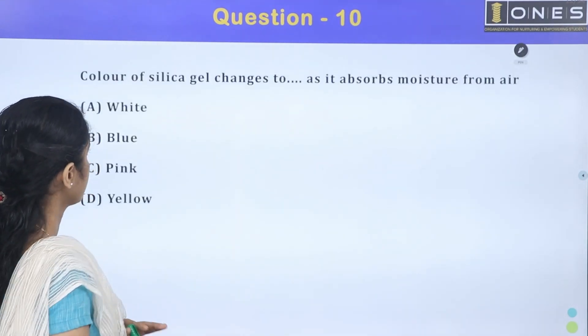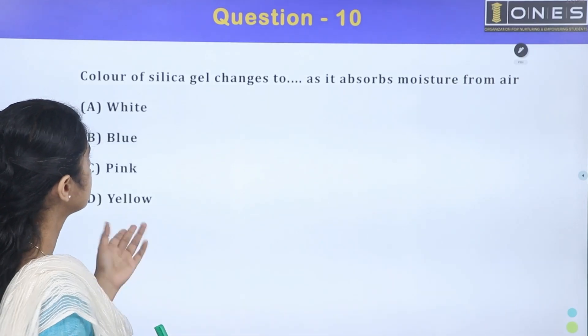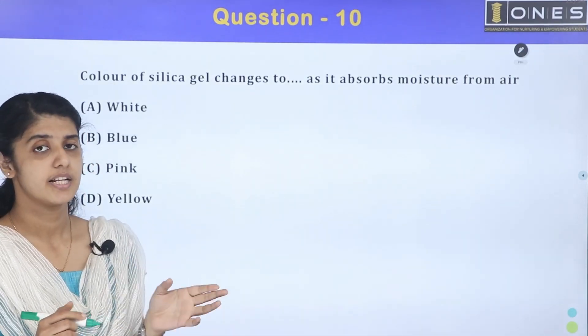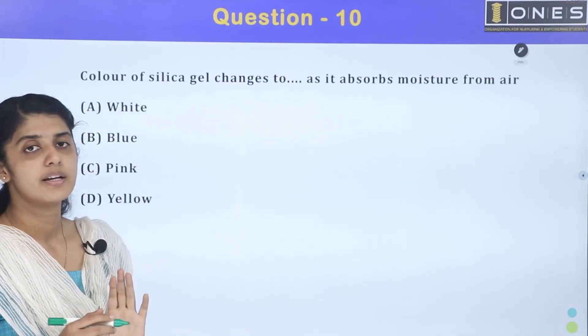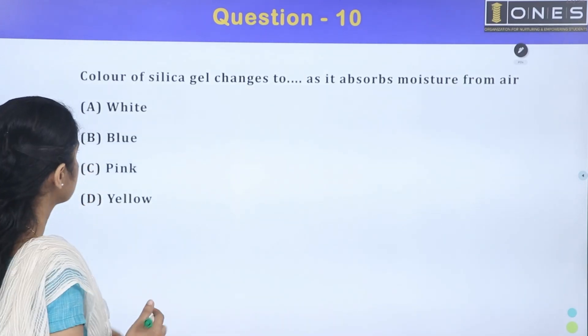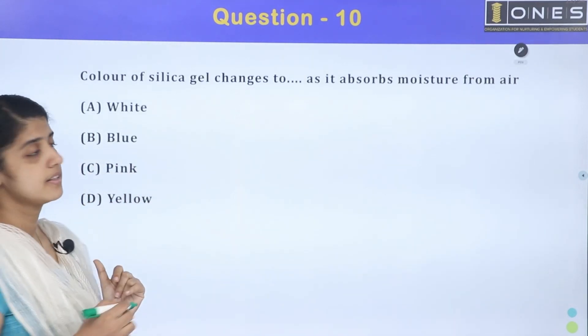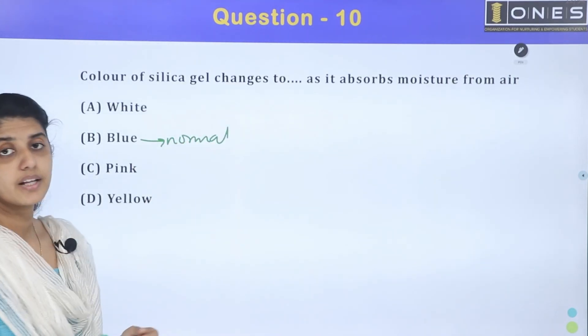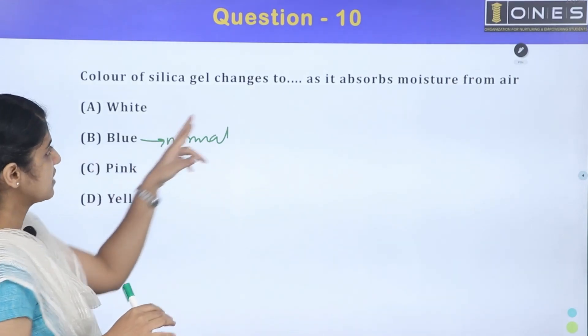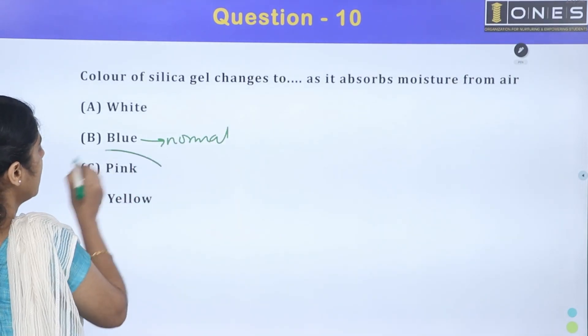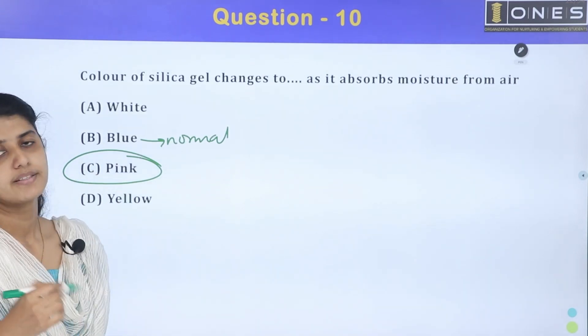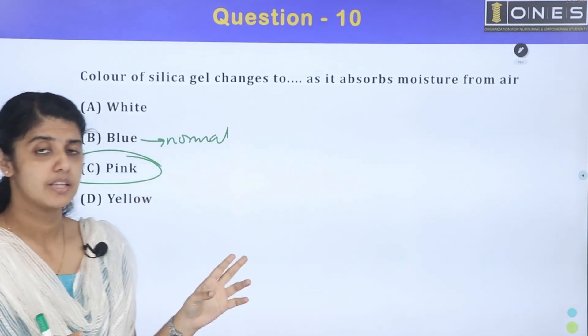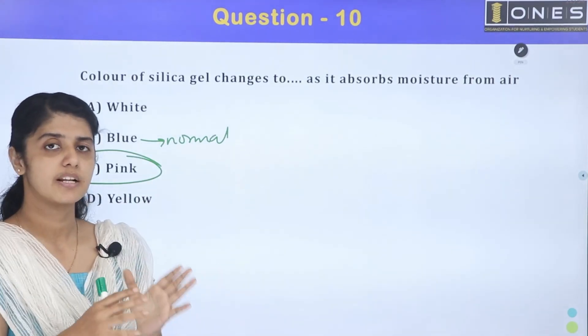Next question: the color of silica gel changes as it absorbs moisture from air. The normal color of silica gel is blue. When it is 50% water-saturated and moisture is absorbed, the color changes to pink. Silica gel is used in breathers of conservator-type transformers.